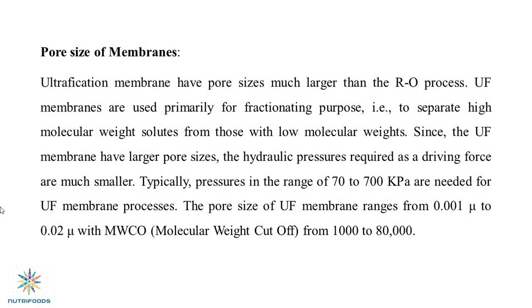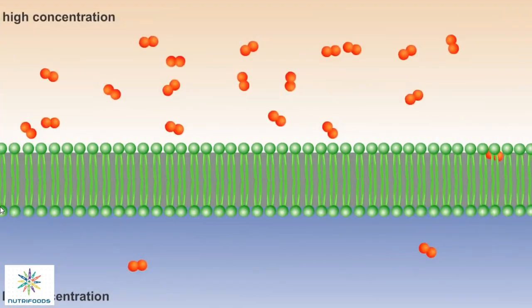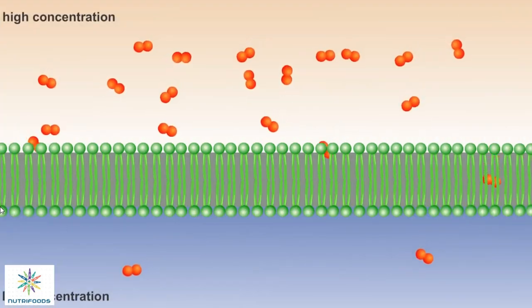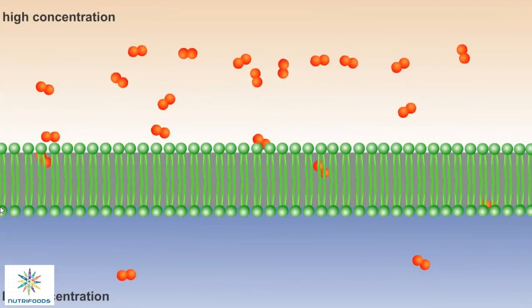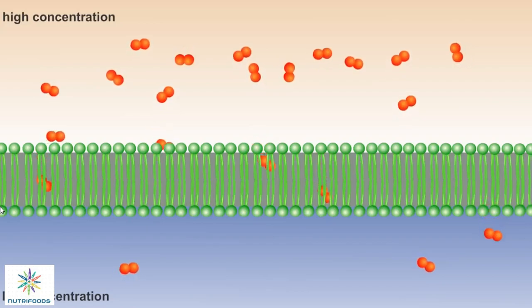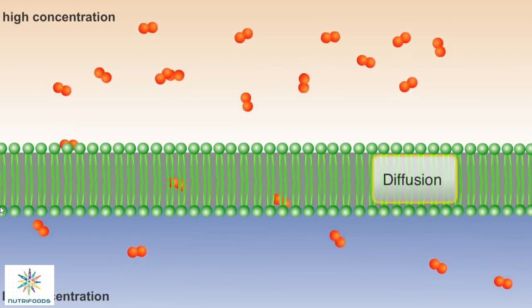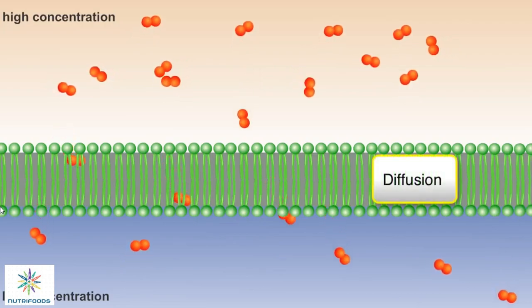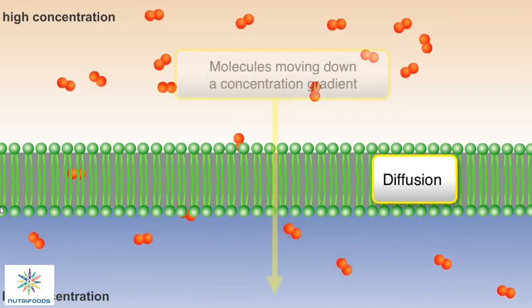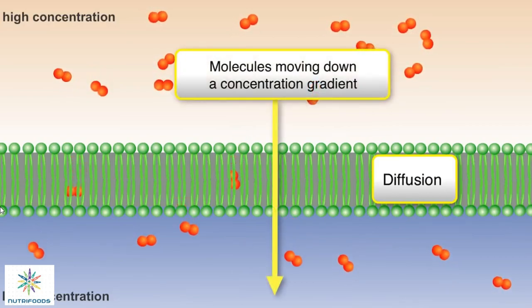Since the ultrafiltration membranes have a larger pore size, the hydraulic pressure required as a driving force is much smaller. Typically, pressure in the range of 70 to 700 kPa is needed. The pore size of ultrafiltration membranes ranges from 0.001 micron to 0.02 micron, with a molecular weight cutoff from 1,000 to 80,000.